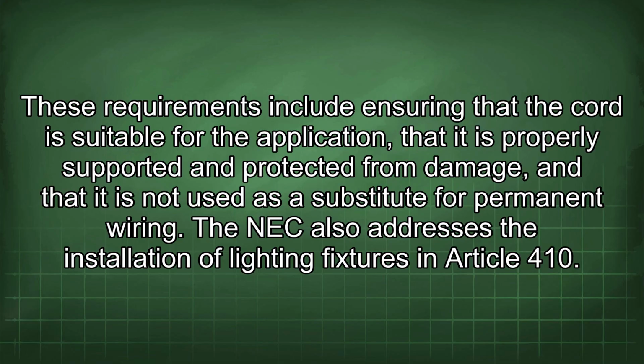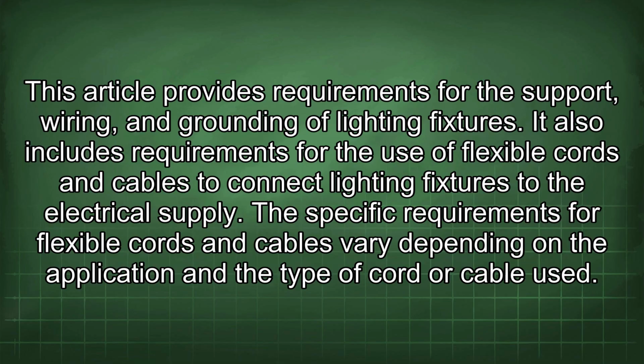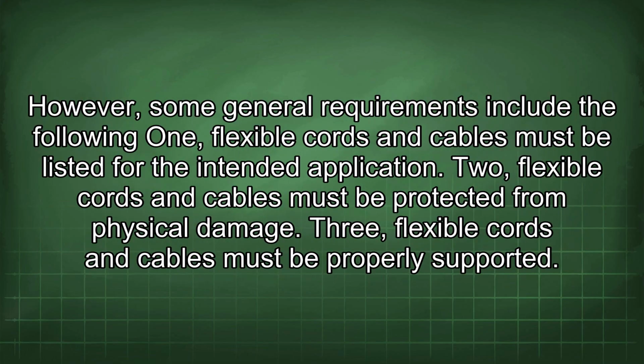The NEC also addresses the installation of lighting fixtures in Article 410. This article provides requirements for the support, wiring, and grounding of lighting fixtures. It also includes requirements for the use of flexible cords and cables to connect lighting fixtures to the electrical supply. The specific requirements for flexible cords and cables vary depending on the application and the type of cord or cable used. However, some general requirements include the following.